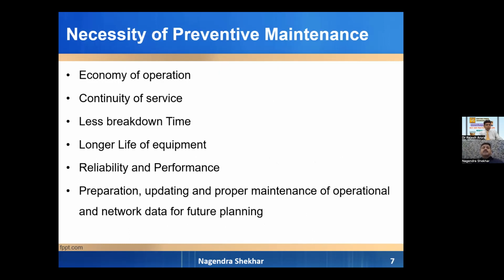Why is maintenance necessary? Number one, economy of operations. When your system runs 24/7 or you put it off as per schedule, the operations are always cheaper. Continuity of services. When you are continuously supplying electricity to your esteemed consumers, it affects revenue, losses, and above all, the esteem of the organization, the brand name. Less breakdown time. As I gave you the example of partial discharge, when you know that a breakdown can happen, you resolve it prior to that. So breakdown time is lesser.